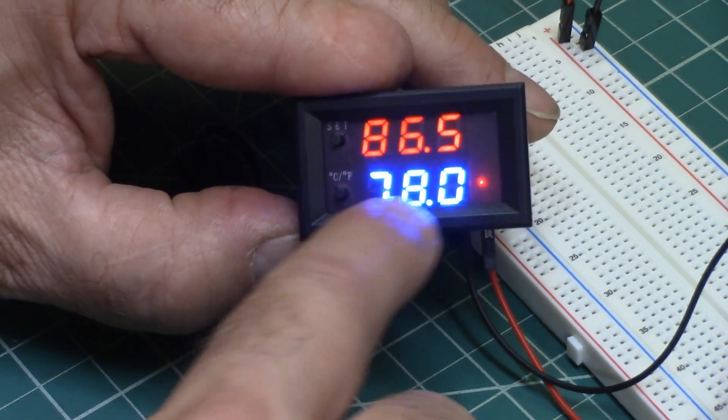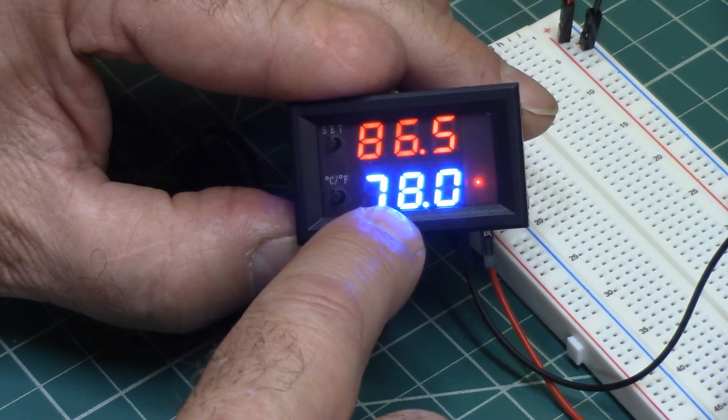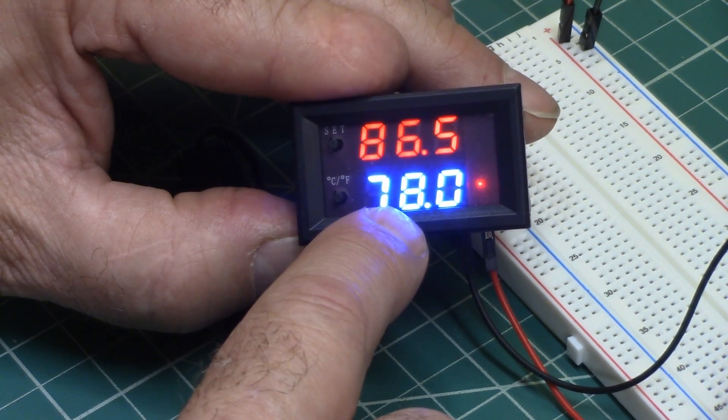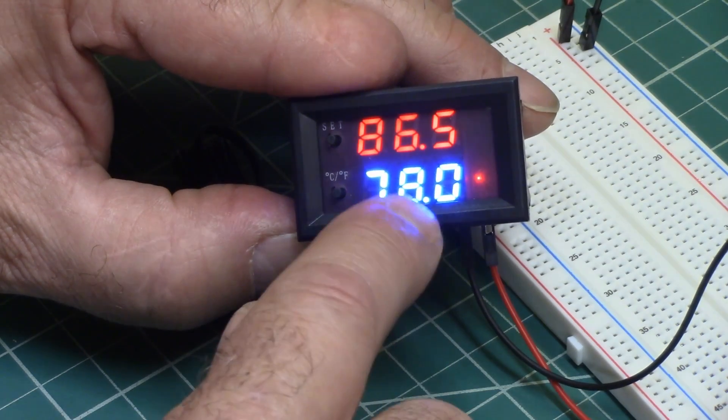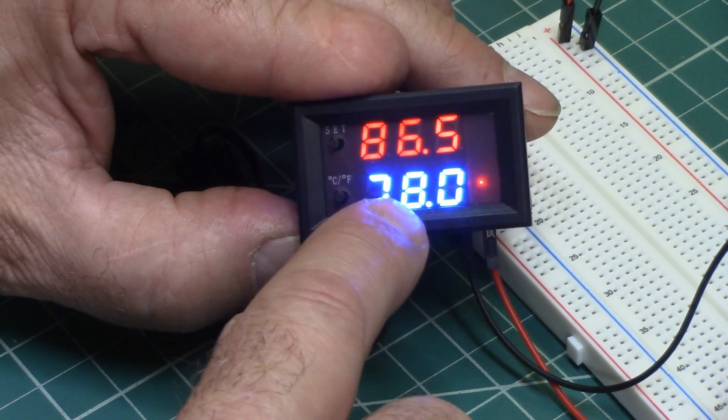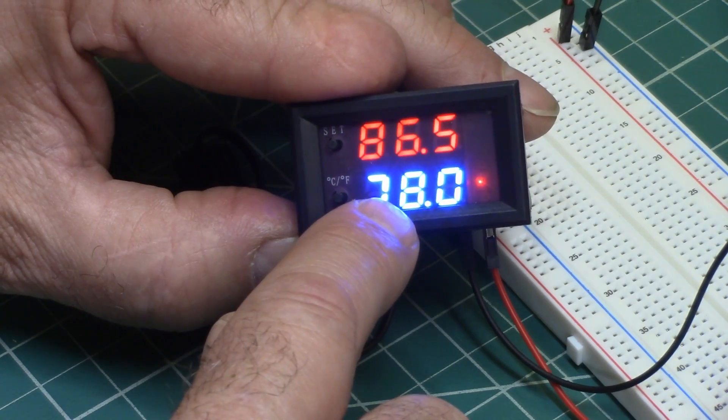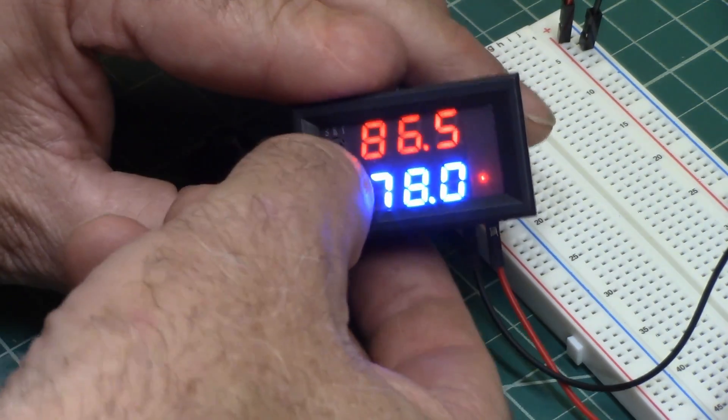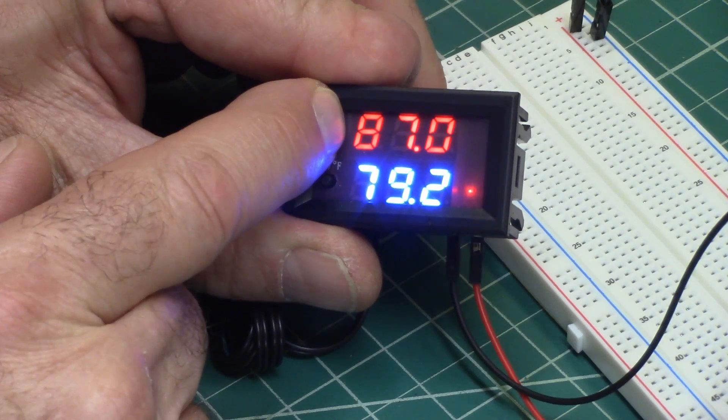So in cooling mode, when the temperature gets hotter than what you've set, it's going to turn the relay on. In heating mode, it's going to turn the relay on when the temperature gets lower than the temperature that you've set. So that's your heating and cooling mode. To get into all the programming, you hold this down for five seconds.